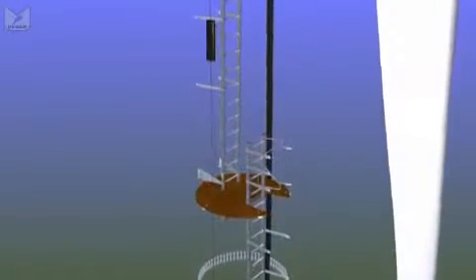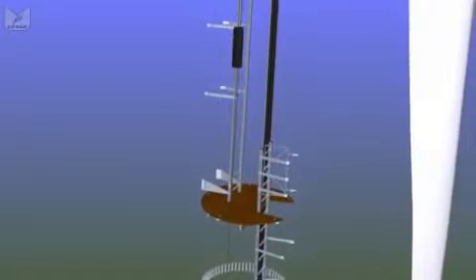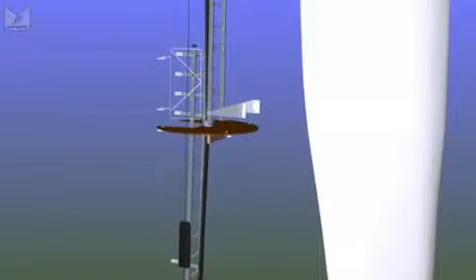But eventually, the main cables stop being attached to the wall, and they hang freely in the centre of the tower, so they can twist as the nacelle rotates to face the wind. If they twist too many times, the nacelle will spin itself around to remove the twists.